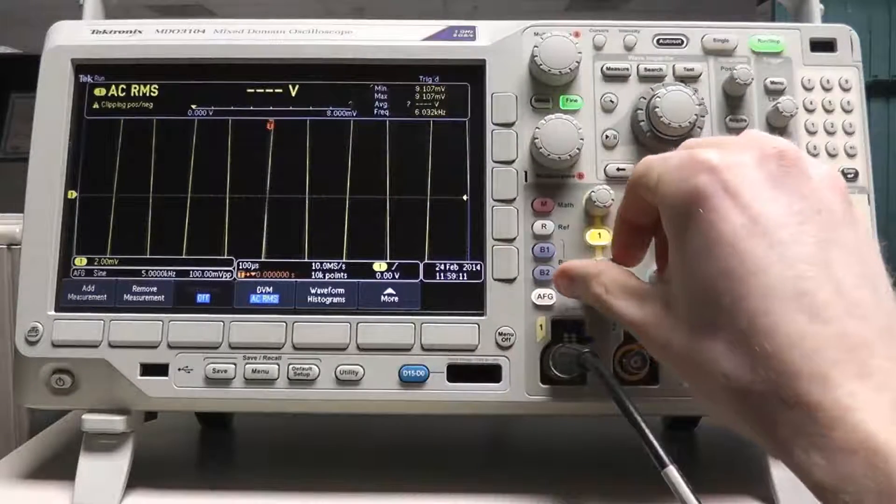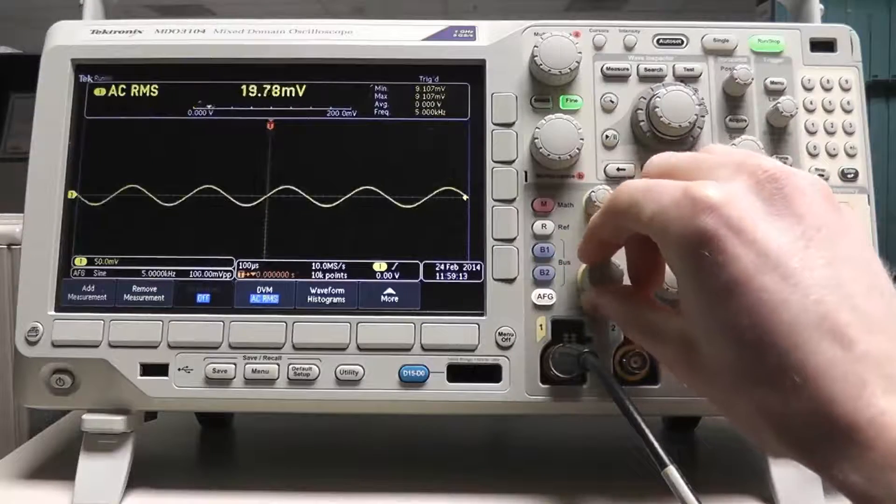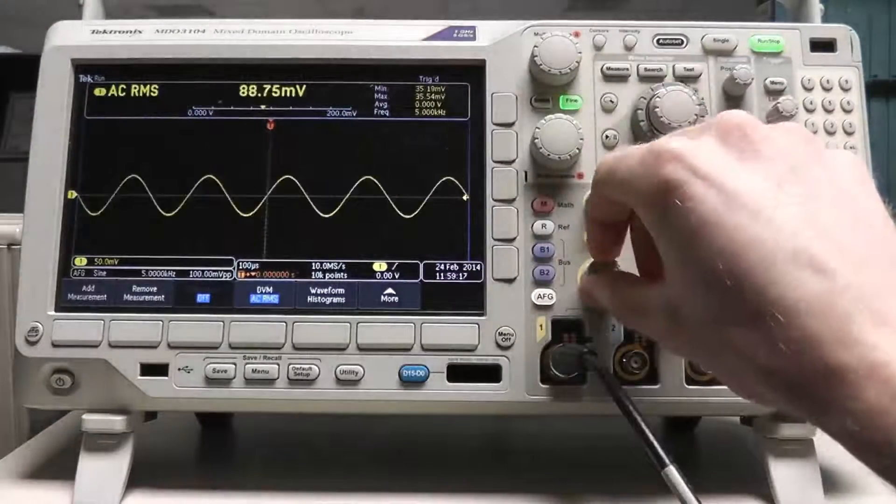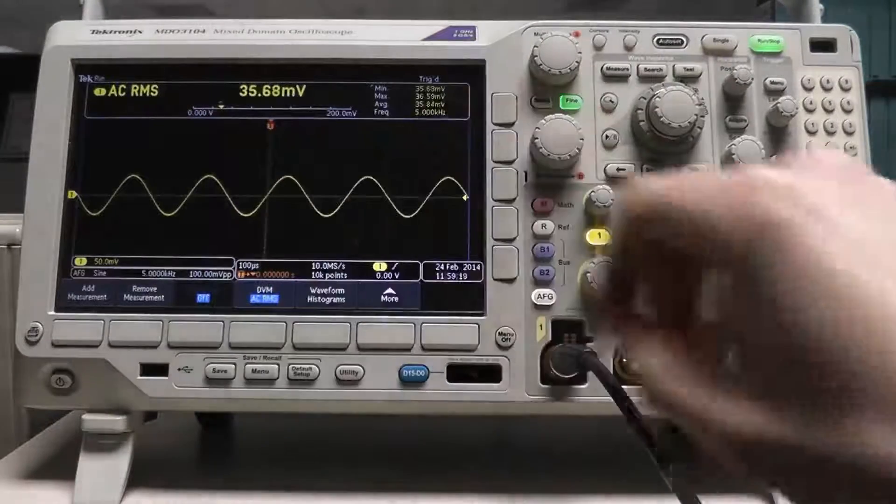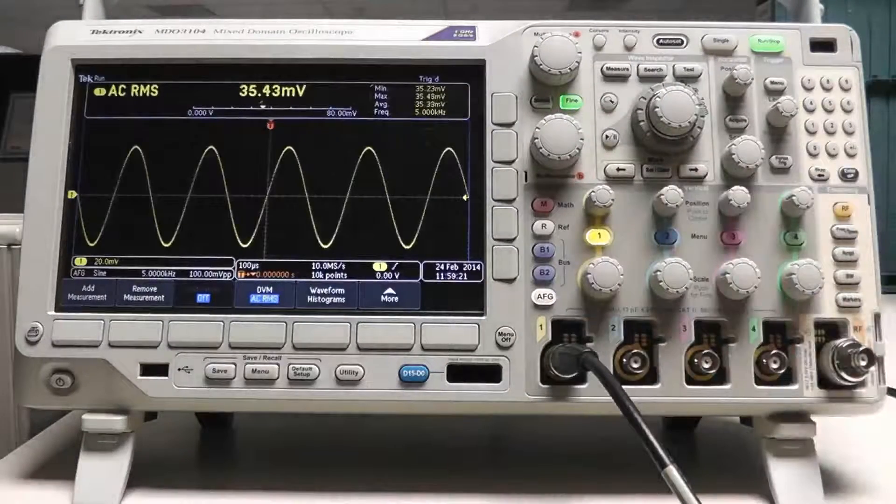You'll notice that changes in vertical scale also changes the DVM range. If the yellow current measurement arrow is visibly within the displayed range, the measurement will have the highest accuracy.